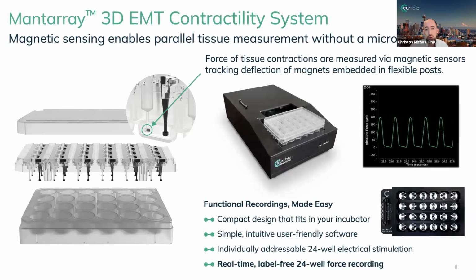If pacing and conditioning is not enough for you, and you also want to get contractile data, that's where we have the Mantarray contractility system. So before I explain the system, let's look at the consumable on the left. So you see the green circle. At the very tip of the white flexible post, there is a black dot.